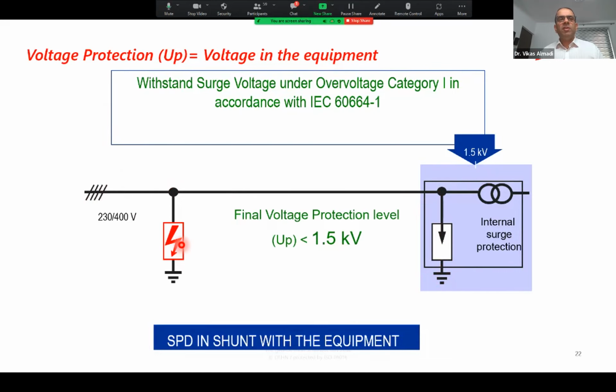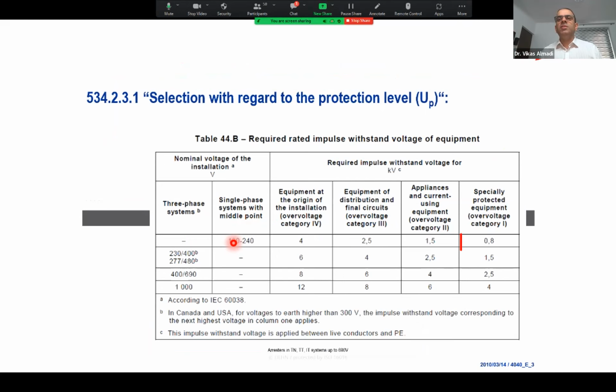So we use some arrestor here. If one arrestor is not sufficient, then we try to parallel it with a lower capacity arrestor. We will come to that, but at the same time, we must look at this. Here I'm talking about the low voltage system, 230/400 V, and IEC 60364-5-53, and this is the chart which talks about 1.5 kV being the voltage we have to maintain, and if we are able to maintain that, then the performance is good. That means the equipment will not be exposed to a dangerous voltage. Higher voltage equipment, basically higher voltage protection levels, are also allowed. So voltage protection level is the voltage that the SPD allows to go inside the equipment. This should be as low as possible. So these are the maximum limits.